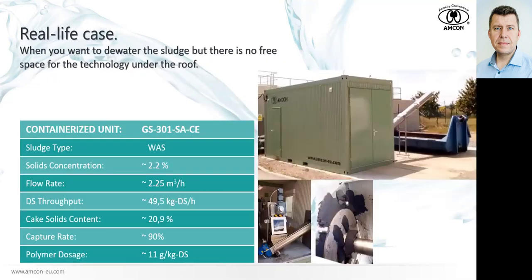There's another special case where the wastewater treatment plant was built without calculating space for sludge dewatering on-site. The solution is a containerized installation — a container with all technology inside, insulated, with heating and lighting — everything needed to process sludge dewatering outside the main building. In this case, a mid-size GS301 machine: waste activated sludge solid concentration 2.2%, capture rate 90%, cake solid content almost 21%, polymer dosage 11 grams — concrete data for a concrete installation.